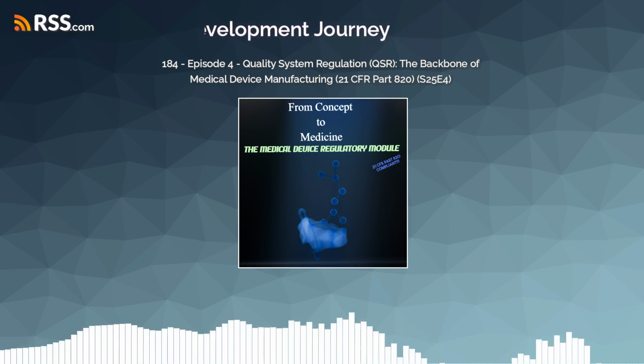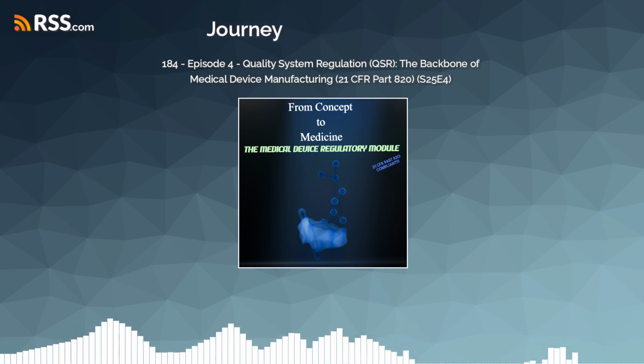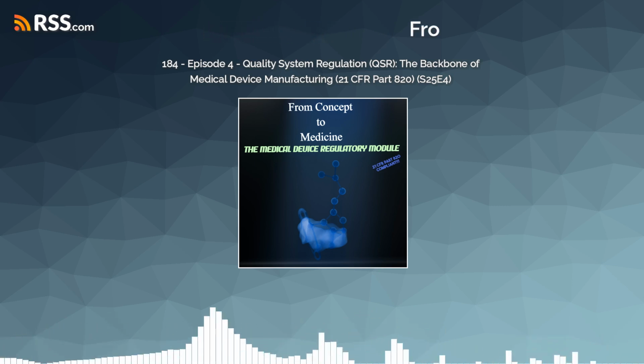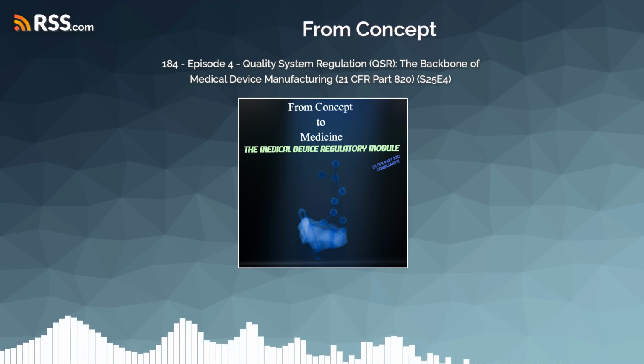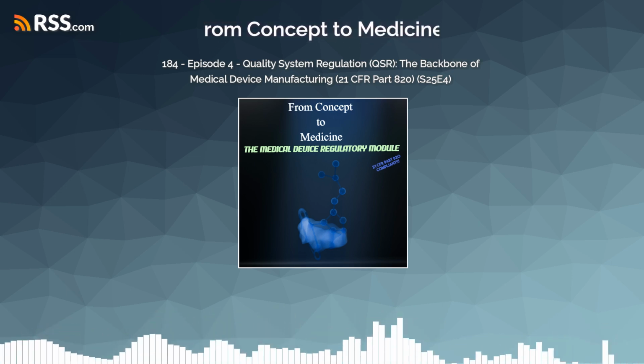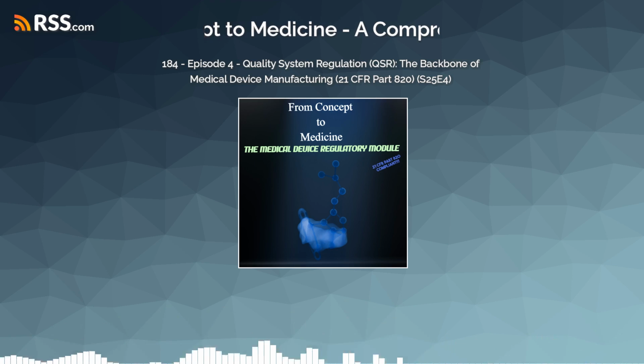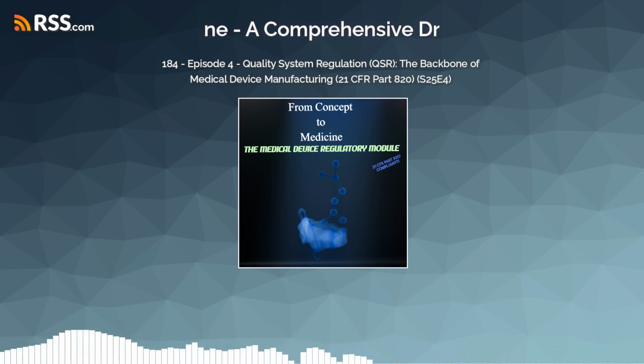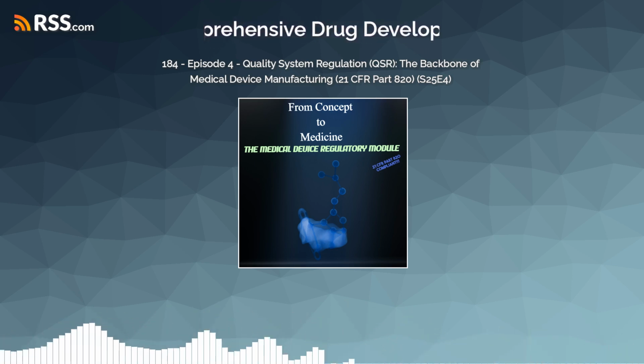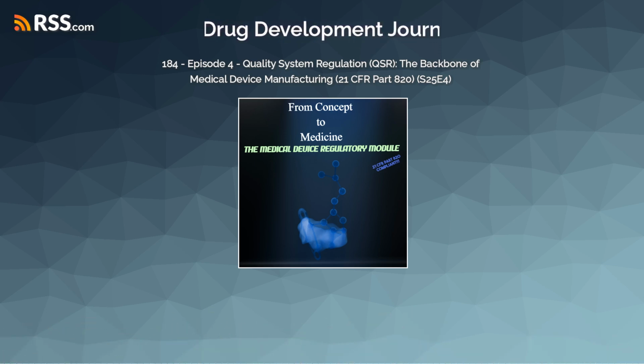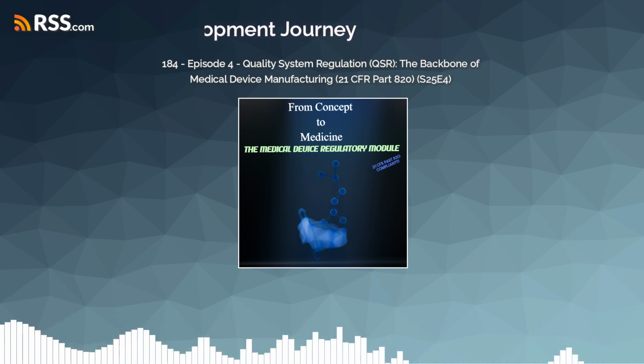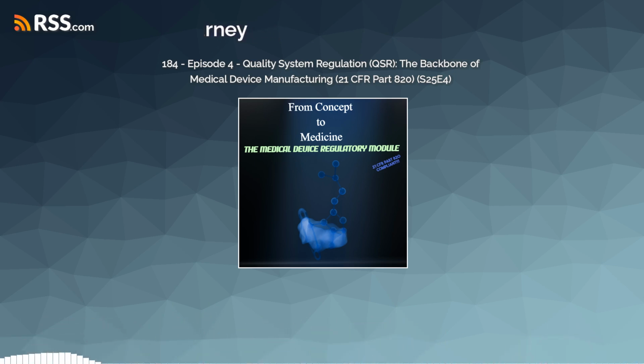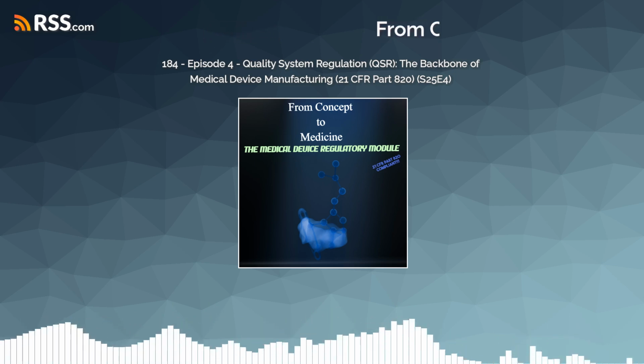Good question. Verification is basically checking. Did our design output meet the input requirements? Did we build the device according to our own plan? Validation asks a slightly different question. Did we build the right device for the user and for what it's supposed to do? So validation often means testing actual production units under real-world conditions or simulated ones. And a huge part of that nowadays is software validation. That's a whole complex area itself.